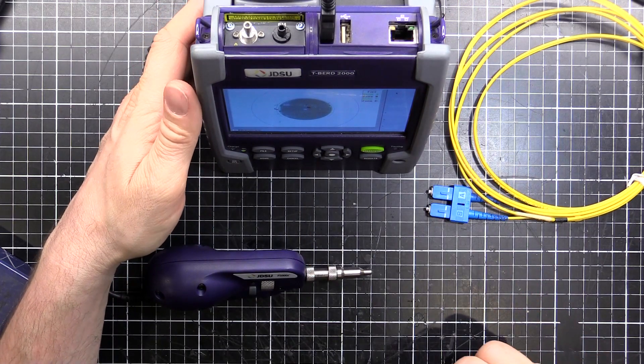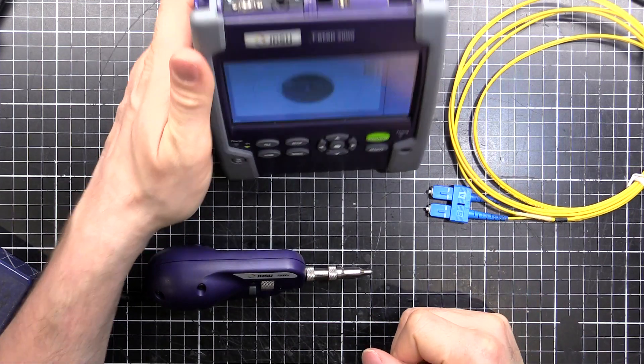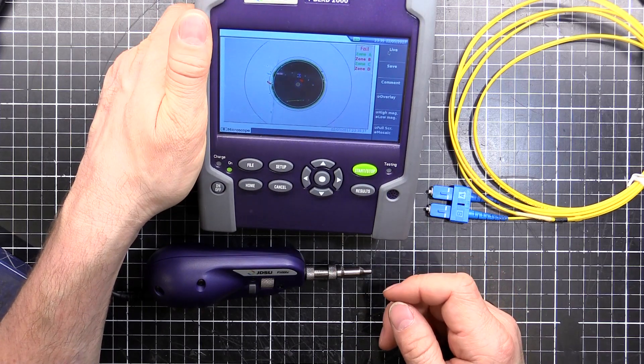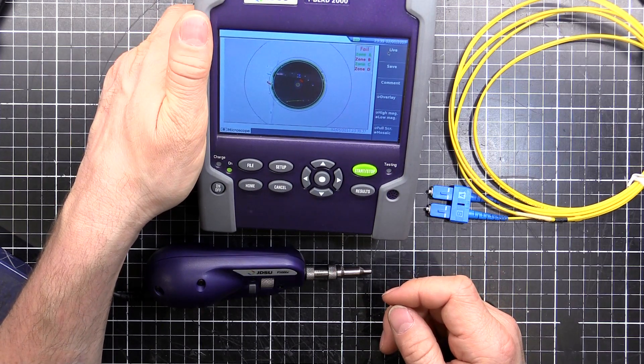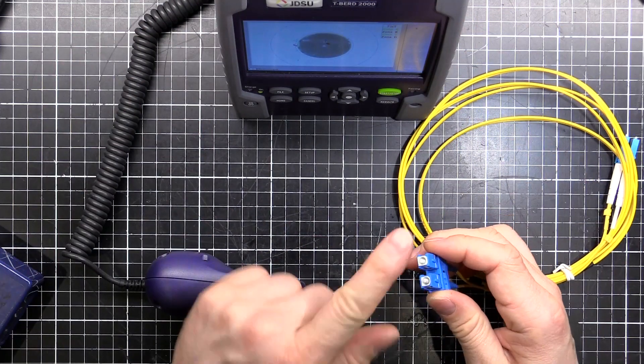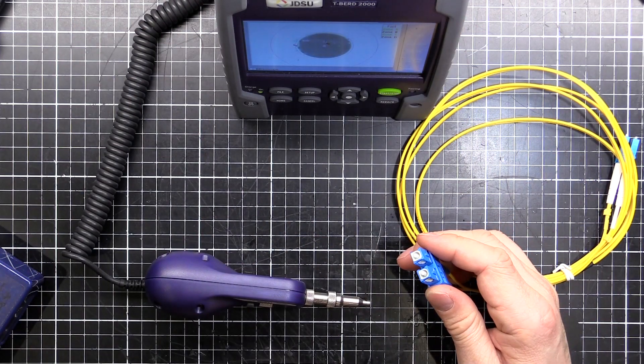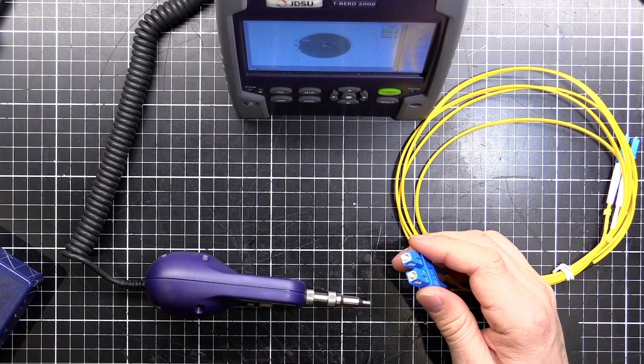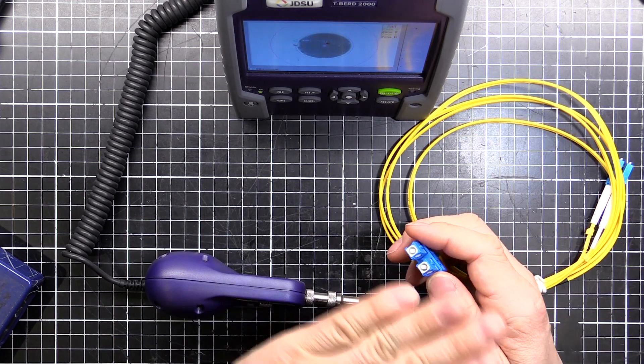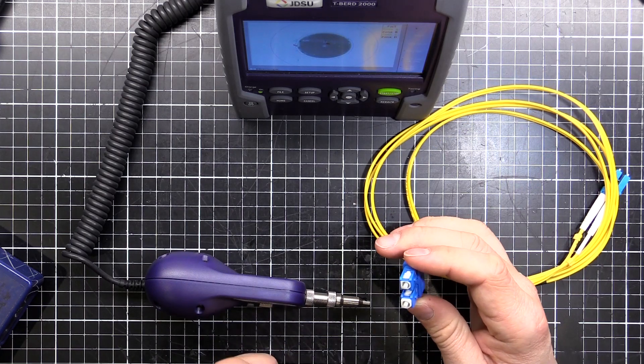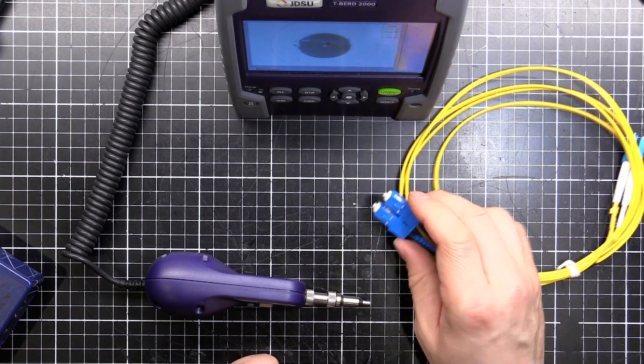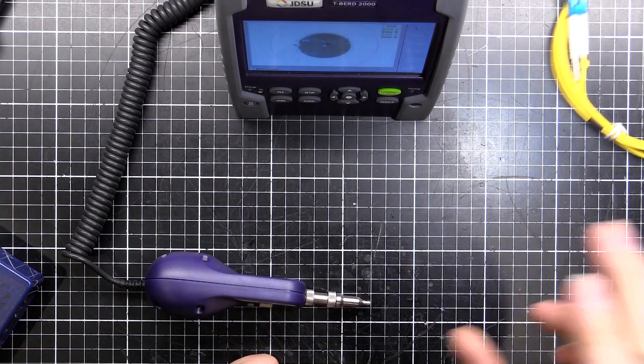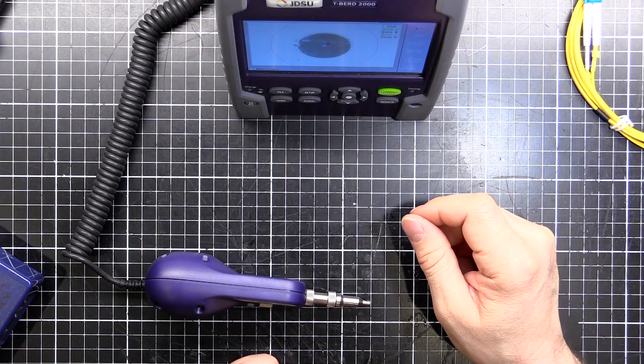So that's the different failure modes that you'll find on one of these things. The shiny bits come up white. The dirty bits come up black. Usually it's easy to clean if it's black. If it's shiny, you might be looking at new fibre. You can polish the end if you need to. If it's like a transit fibre that you can't replace because it's hardwired into the building or something, then yeah, you'd be looking at getting your polishing kit out and cleaning the end. But for a cable like this, you just throw it away, get another one. It's not worth the time really.